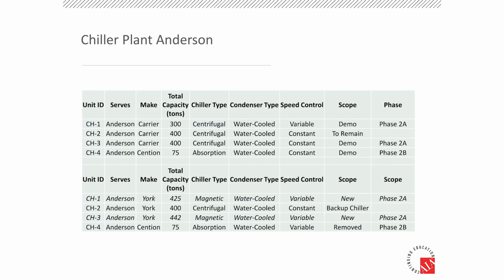Here's the Anderson plant, including the constant speed absorption machine. The funny thing about that ECM when it was done in the previous energy service performance contract is that the cogen machine that's on top of Anderson cannot run outside of occupied hours. It generates more power than the building uses. So it can only run from 8 to 5. And it can only run when, well, it's a Jenbacher. So it can only run when Austria sends it parts.